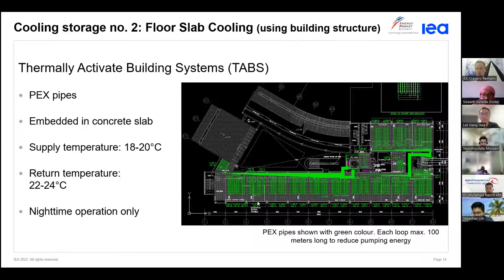And the advantage of this kind of floor cooling system is that it increases the chiller efficiency, because the lift of the chiller is significantly reduced, in this case by about 13 degrees. Instead of supplying 6-degree chilled water, which is very standard for most chillers, 6 or maybe 7 degrees, now we only had to supply 19-degree water. So that is a lowering of the lift of 13 degrees. And therefore the chiller efficiency, this is the Carnot efficiency on the right, which is the theoretical maximum efficiency of chillers, basically doubles, a bit more than doubles.